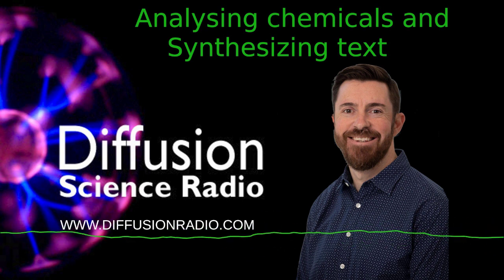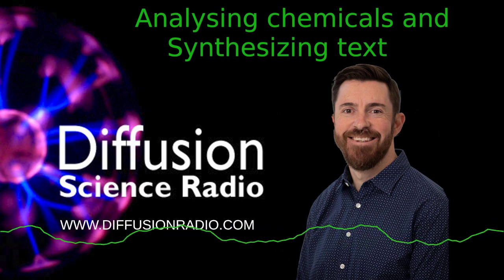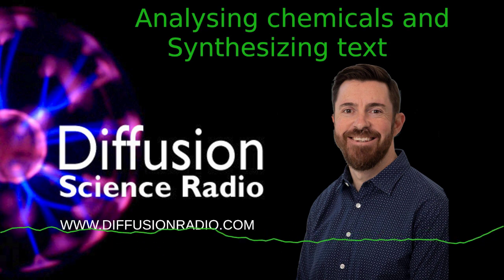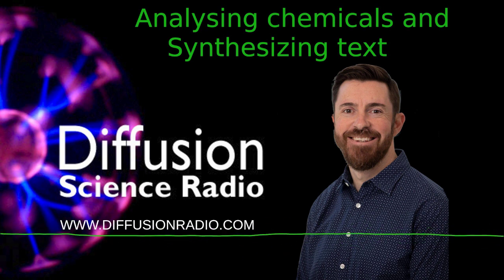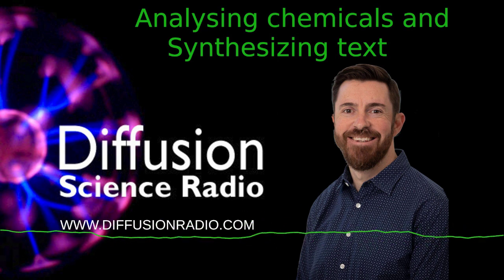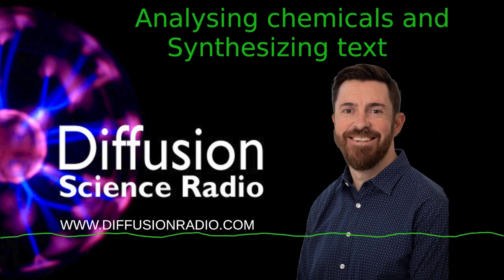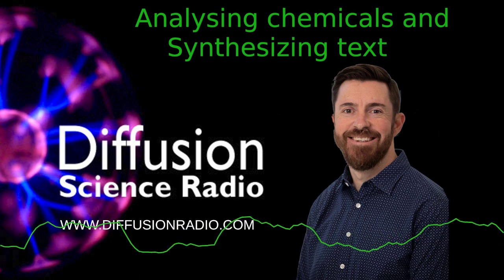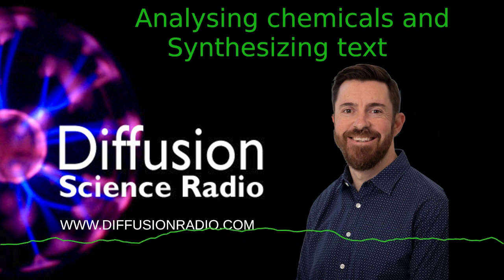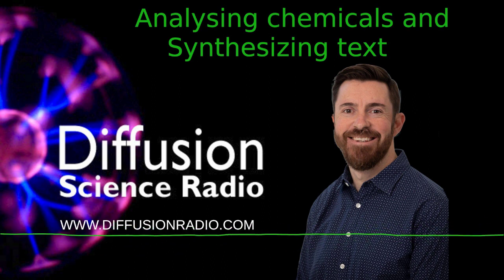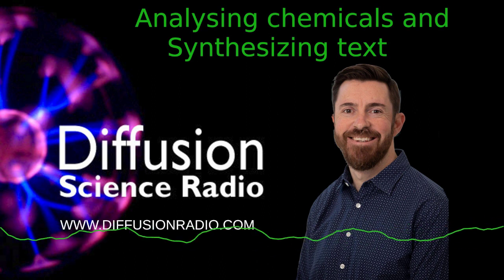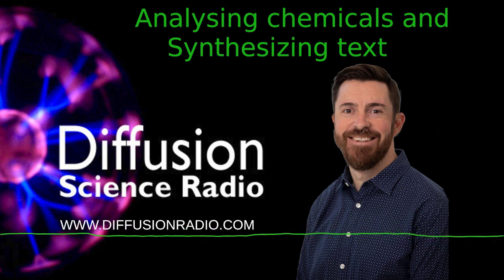And how big are these devices? So as I said, they're benchtop detectors. So we're looking at something which has a footprint of 1 metre by 50 by 50 centimetres. So if you were doing environmental investigation, you could take one on site? There's a number of resources necessary for this instrument to run, which means that it is not really suitable for taking on site.